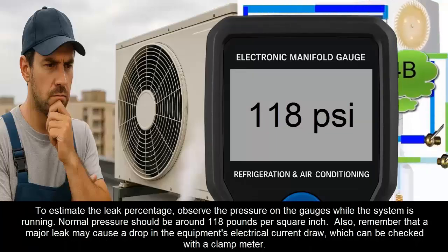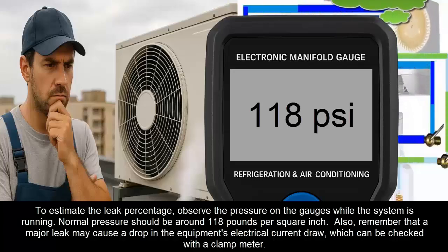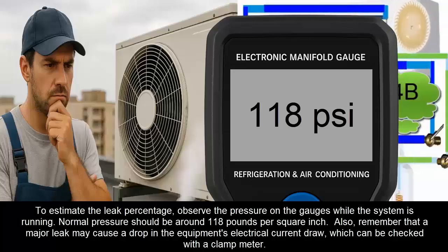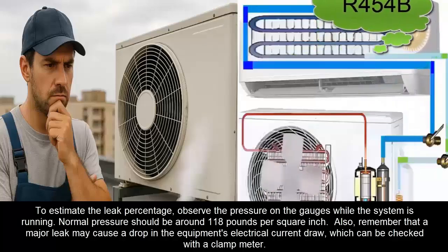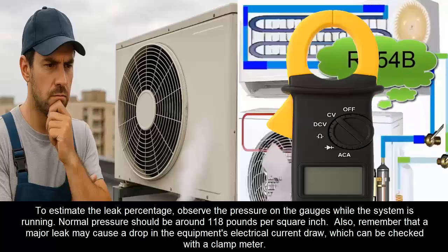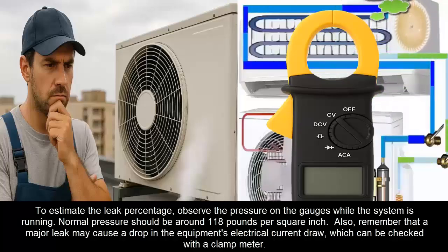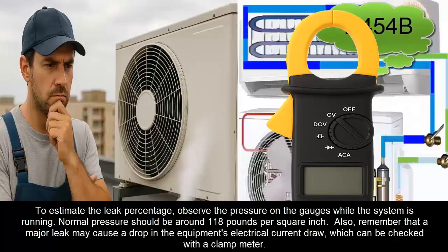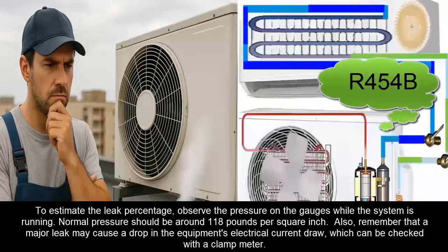To estimate the leak percentage, observe the pressure on the gauges while the system is running. Normal pressure should be around 118 pounds per square inch. Also, remember that a major leak may cause a drop in the equipment's electrical current draw, which can be checked with a clamp meter.